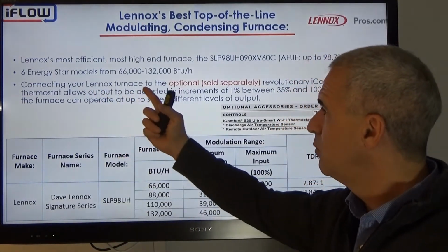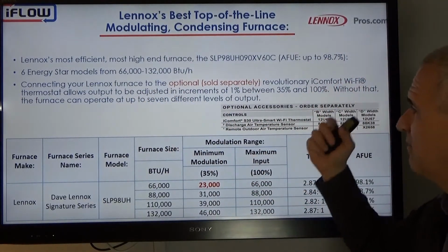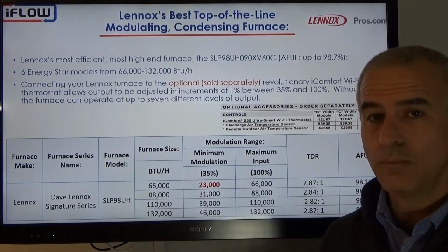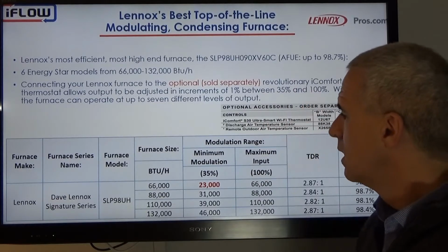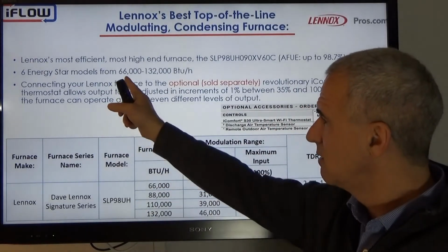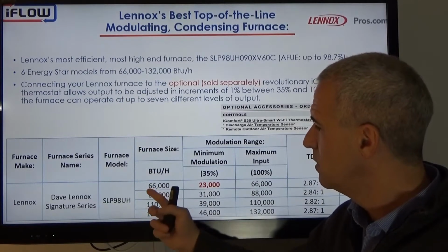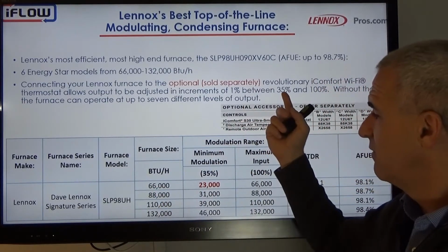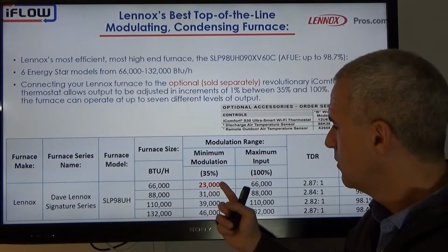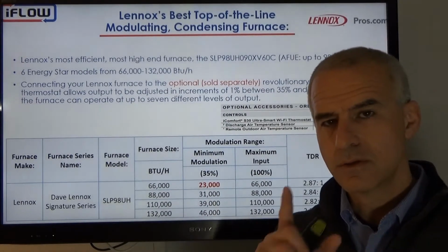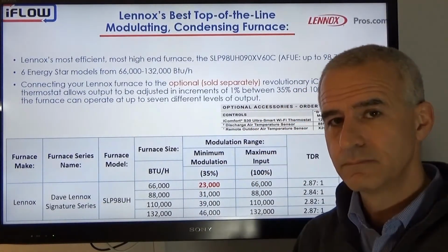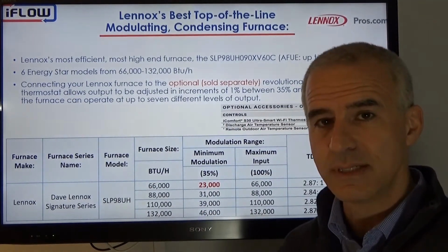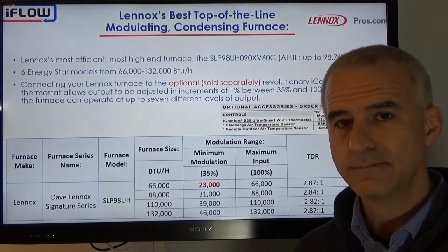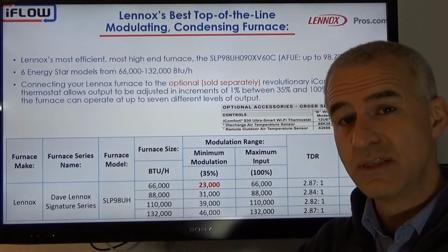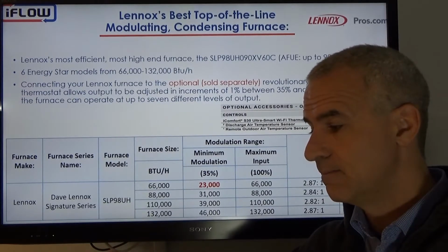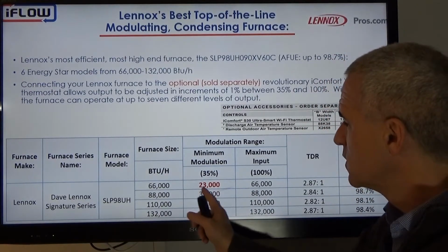Then it says if you purchase the optional iComfort Wi-Fi controller, you can then adjust your unit in 1% increments between 35 and 100%. So to see what that minimum input is, we took the furnaces, so we have 66, 88, 110, 132. Those are the maximum inputs. Multiply it by the 35%, assuming we buy the controller. Then we can modulate down to 23,000 BTUs. So the best furnace on the market in terms of AFUE can only modulate down to 35%, which is 23,000 BTUs. It cannot go below that. Now compare that to 10 or 13,000 BTUs that we can get off the 240A2, for example, or S2. So this is where we're going with it.